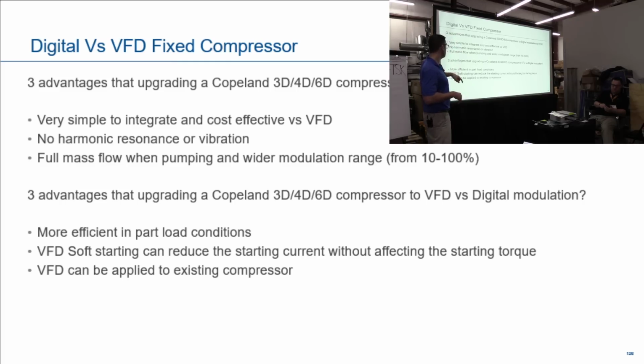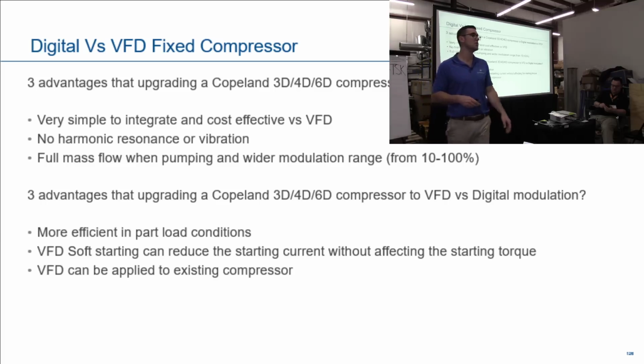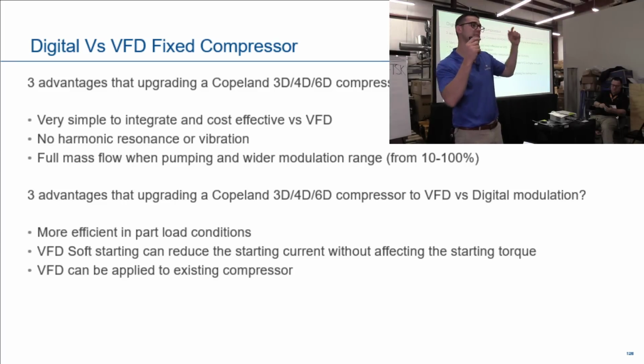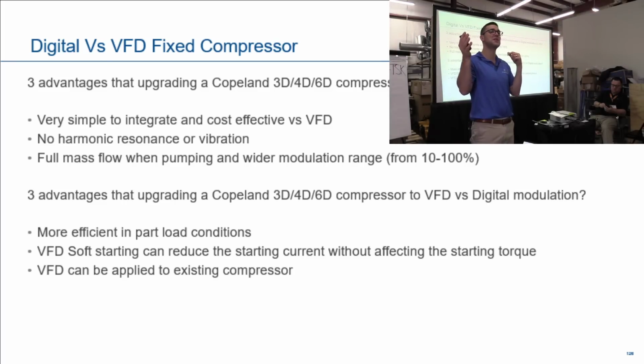But on the variable speed side, you get better soft starting, it can be applied to an existing compressor like we talked about, and it's more efficient at partial load. So now you have to think about the application. Should I be using digital or variable speed on that Copeland compressor?